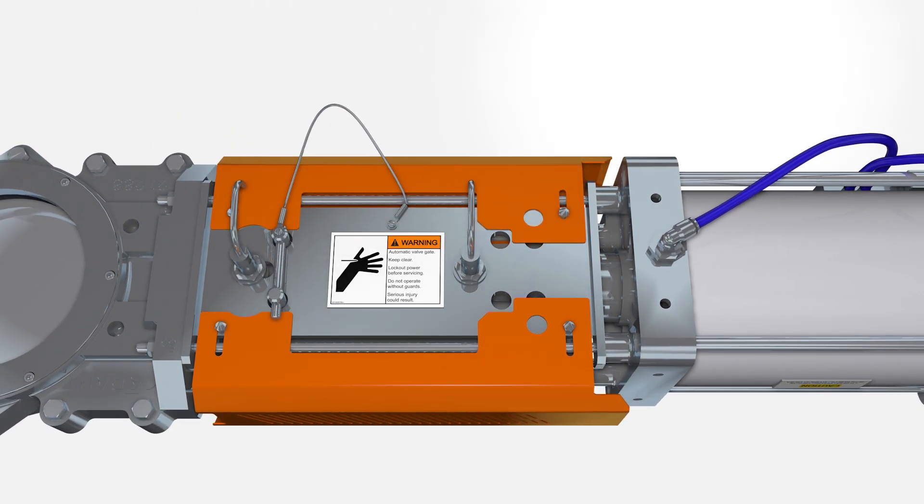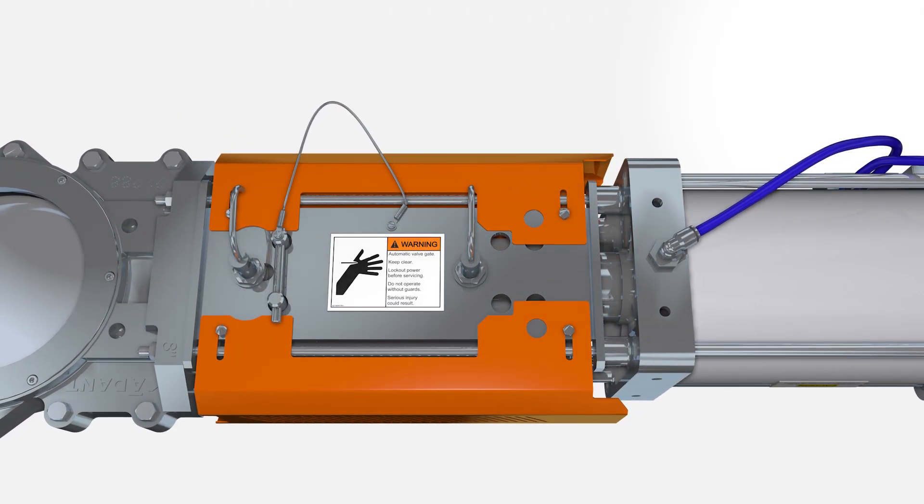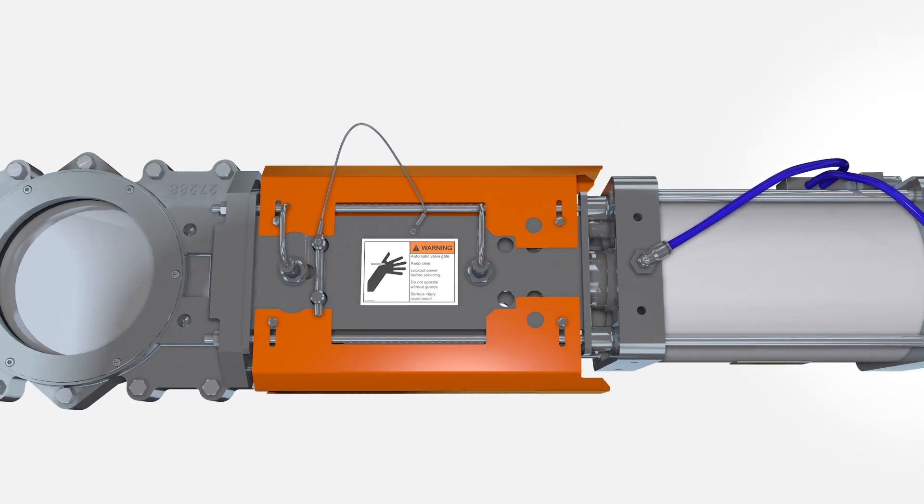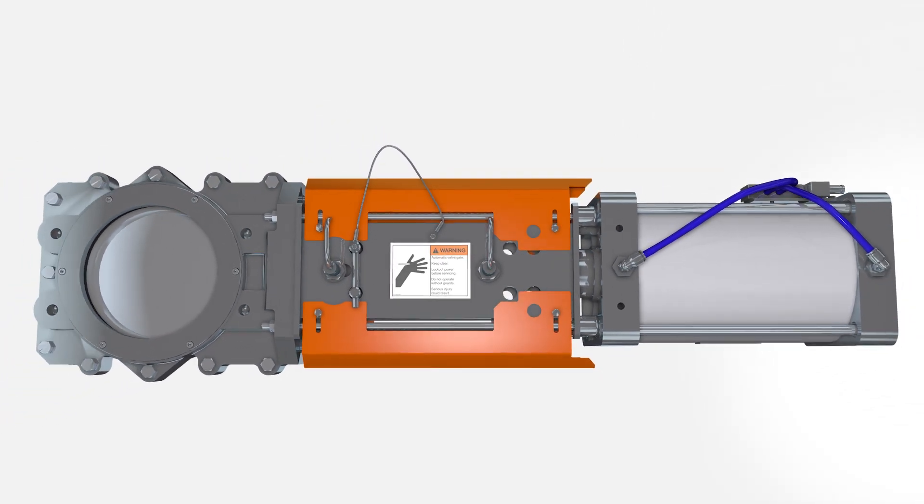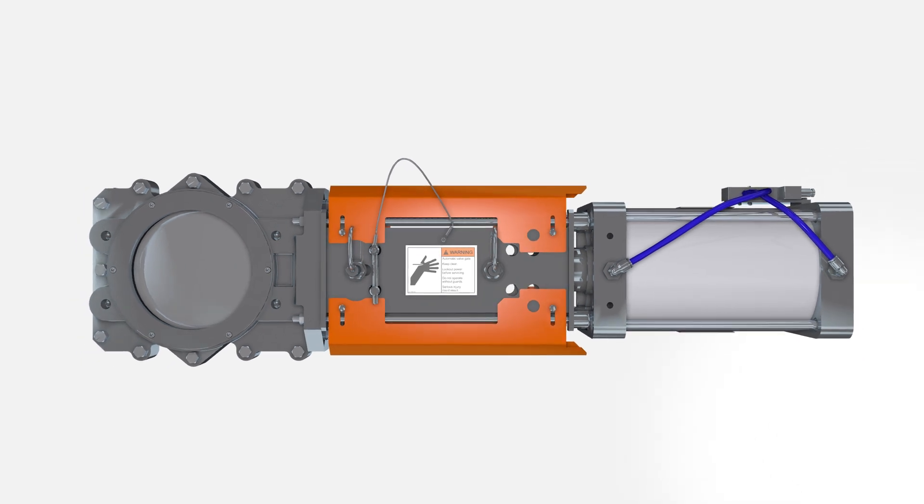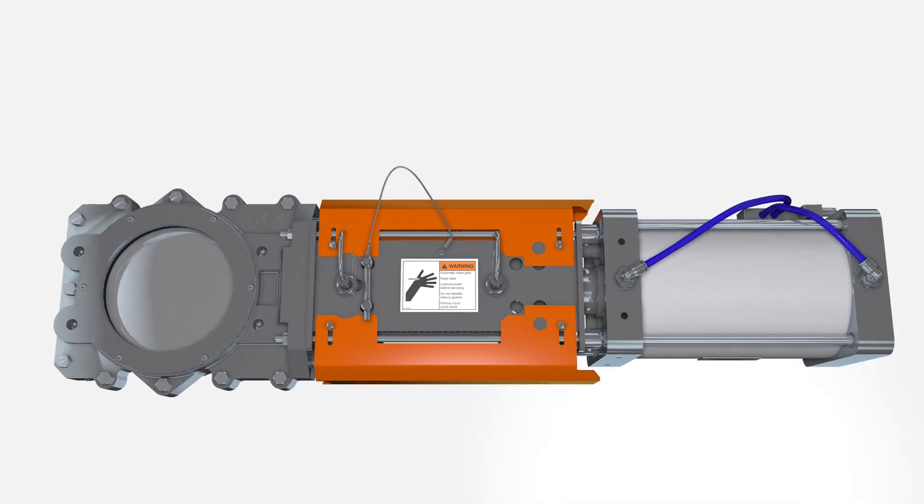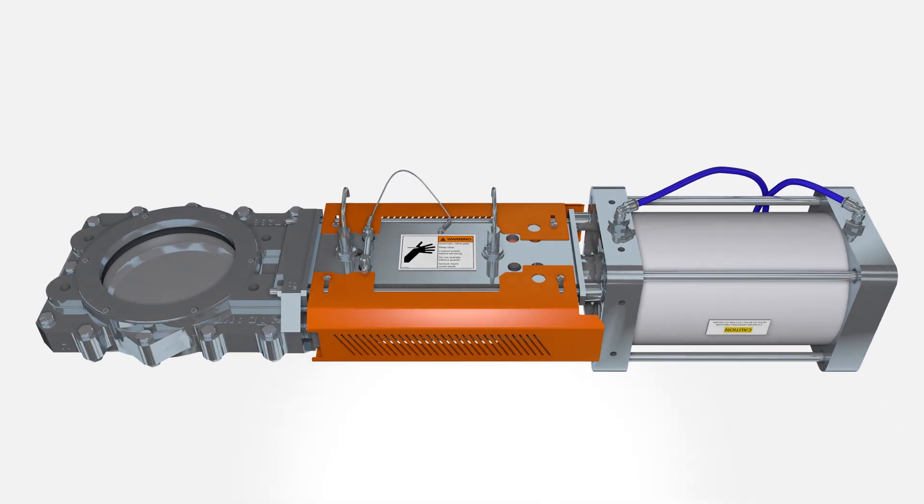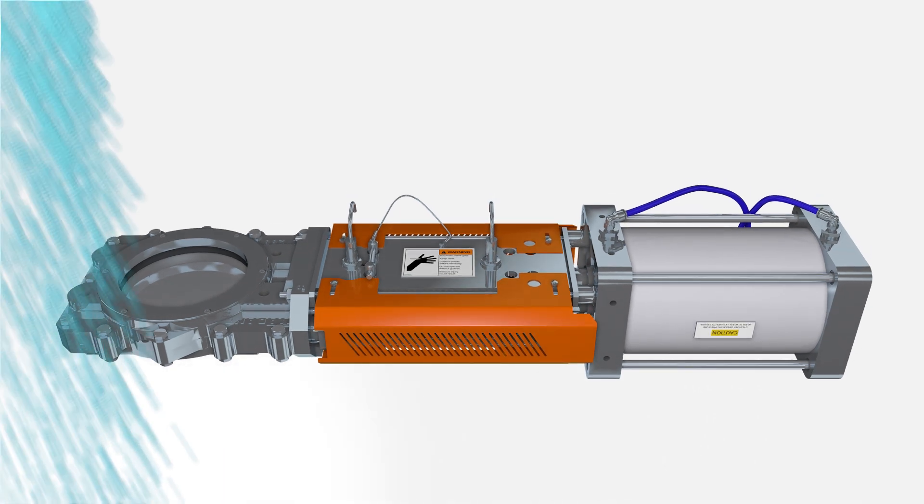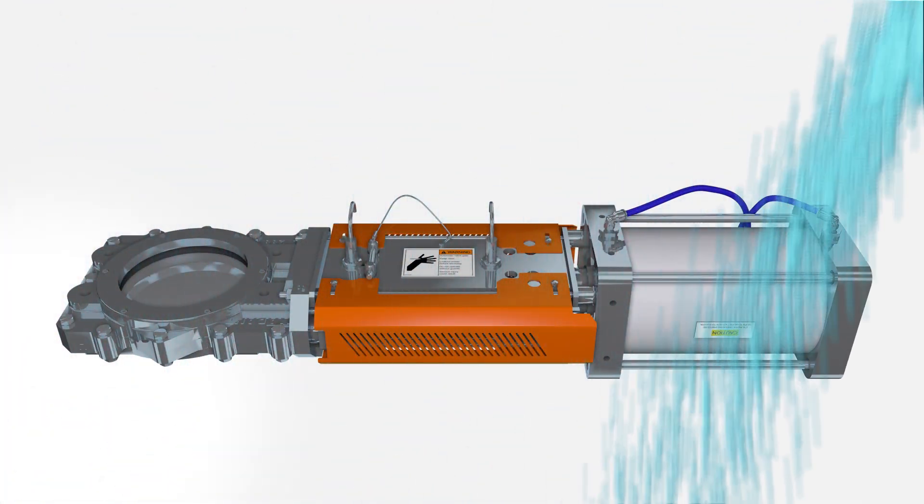Follow safety standards to a zero energy state. Disconnect the pneumatic lines from the control valve assembly and electrical power from the two proximity switches. Place the unit on your work surface with the round side of the valve body assembly facing up. Clean the unit, removing any debris build up.